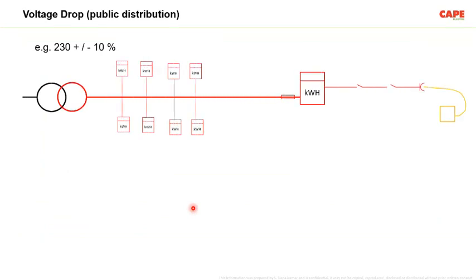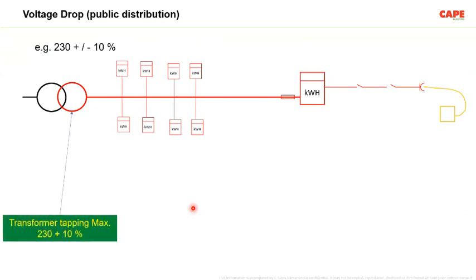Sorry for that. Now, how foreign countries think about voltage drop is, for example, say our voltage is 230 plus or minus 10%. Just take an example. What they say is, at the transformer, if you put the tapping to the maximum, your voltage output at the transformer is 230 plus 10%. You can make it in order to ensure that the last consumer during the peak hour is able to get 230 minus 10%. The last consumer, you must supply a voltage up to 230 minus 10%, and not more than that.